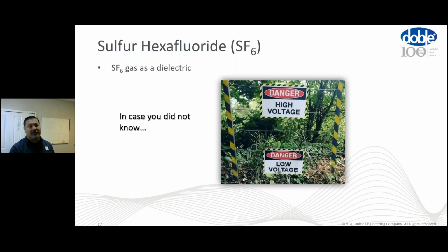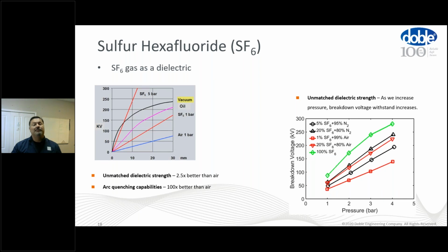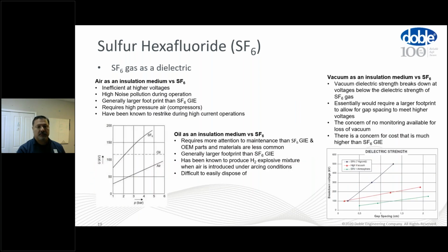Let's talk a little bit about it as a dielectric. In case you didn't know, high voltage, low voltage. SF6 is found in high voltage and medium voltage equipment, not so much low voltage. As you see on the graph on the left side of the screen, as the kV rises and the gap increases, SF6 is an excellent dielectric. Even at 1 bar, which is 14.5 psi, SF6 is still a much better dielectric as the voltage goes up. Even at 1 bar, it is much better than air as an insulator. You can also see on the other side of the slide, at different percentages, different mixes, its ability to not break down as easily under high voltage as pressure increases.